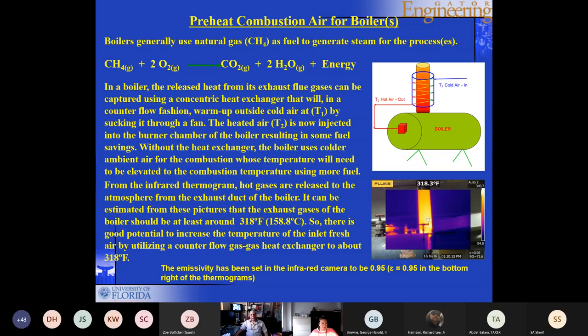So in the boiler, the released heat from its exhaust flue gases, what you do is you put a heat exchanger on top of that boiler, and basically you get the air to shake hands with the flue gases. So you're preheating the air from energy that's already going to go to waste. If you assume that the temperature of the outside air is T1 and that you want to get it up to a T2, and you're looking at possibly 315 degrees Fahrenheit.